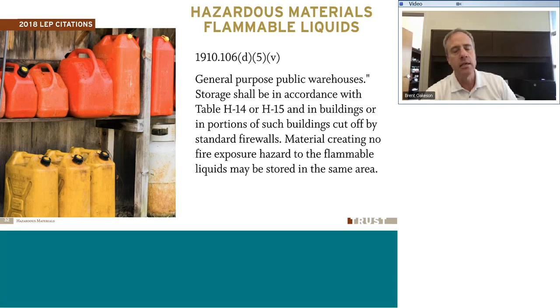But 3 to 5 gallons, we probably shouldn't have any more than that, we should be less than that. What we may have is some portable fuel cans, and those need to meet a certain safety standard to be in use. The best thing is to have a specific area where you store flammables that is rated for flammable storage. It could be a flammables cabinet, or part of your building that is actually constructed and engineered to contain those flammables.